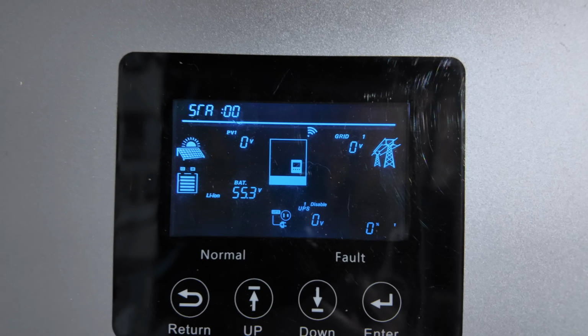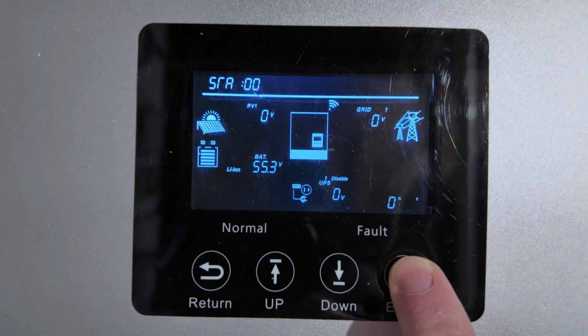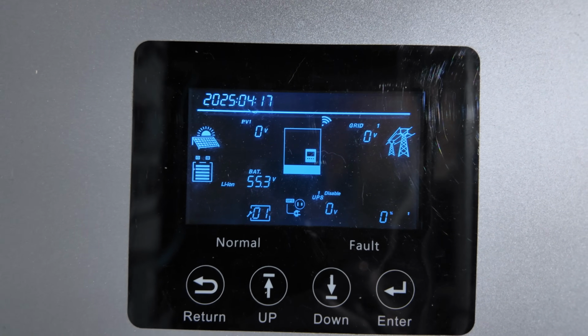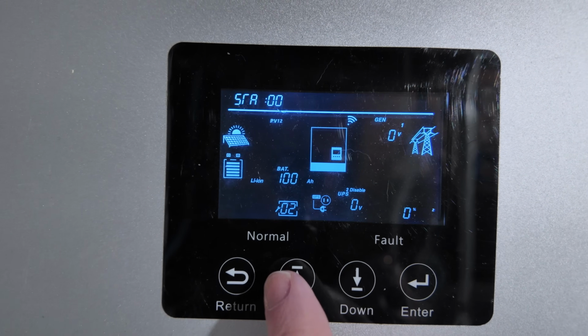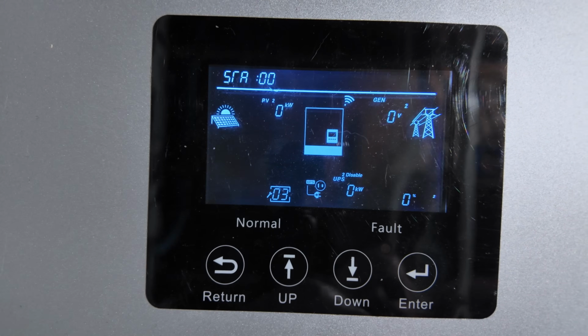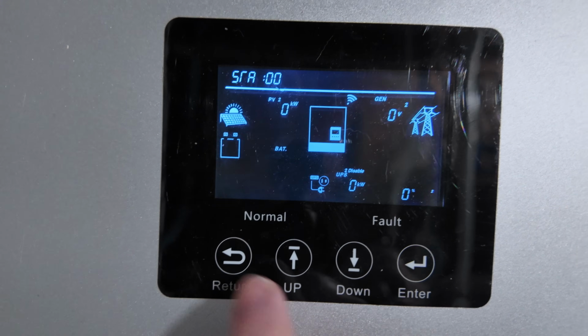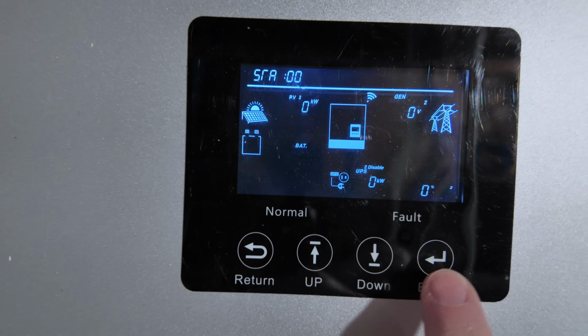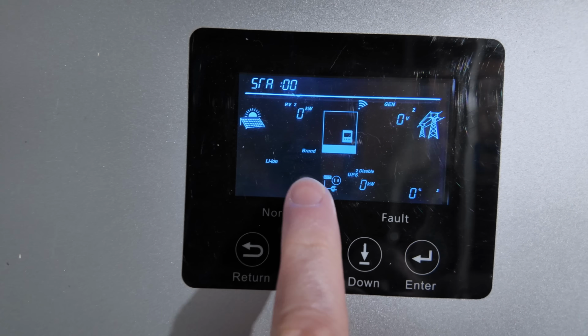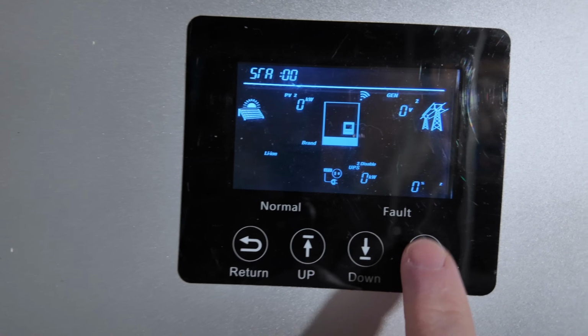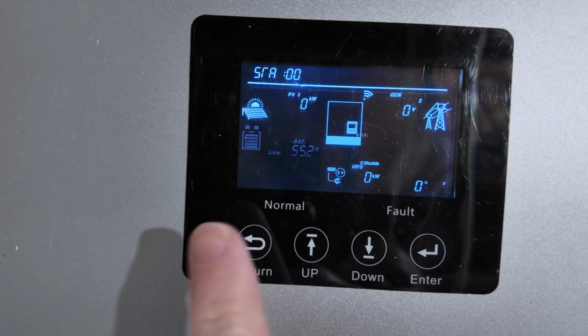If by chance your inverter is not set to the proper protocol, press and hold to enter. To go into the menu, you'll hit up 3 times to get to your battery settings. Hit enter. You want the type to be lithium ion and brand to be 0. Then you can back out.